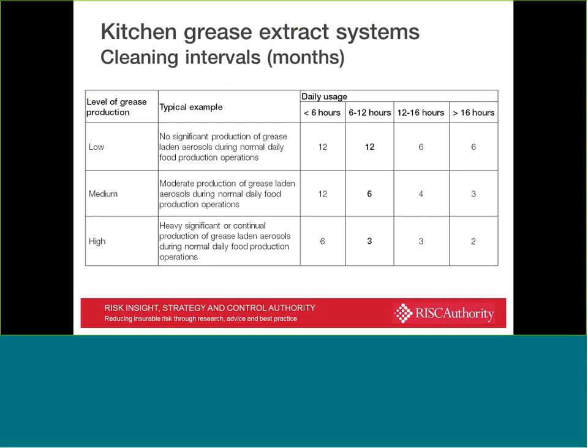And looking at TR19, it provides us with this particular guidance in terms of the levels of grease production, which they classify as low, medium and high, give some typical examples, and then relate that to the daily usage in terms of hours of each system, and then propose cleaning intervals in terms of months. As you can see there, it varies quite widely, but where you've got a system that is used between 12 and 16 hours a day, for example, where there's heavy, significant or continual production of grease-laden aerosols during normal operations, then you should be looking at a full clean of the extract systems every 3 months, rather than at a lesser frequency.